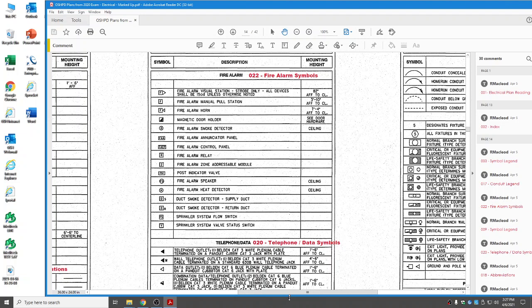Then we've got our fire alarm smoke detector, which is just a circle with a D for a detector. They do have one down below here that's an H for a heat detector. So when you're looking for the circle, you've got a circle D or circle H. Then you've got a fire alarm annunciator panel, fire alarm control panels, fire alarm relays, fire alarm zone addressable modules. Post indicator valves would be a fire alarm coverage for a riser standpipe, for instance, or at a valve location. It'll alert you when that valve is closed off. Then you've got a fire alarm speaker, FS. You'll see that quite a bit in the corridor areas. Then you've got a duct smoke detector with an S next to it, which stands for supply duct, and a rectangular D with an R for return, a duct smoke detector.